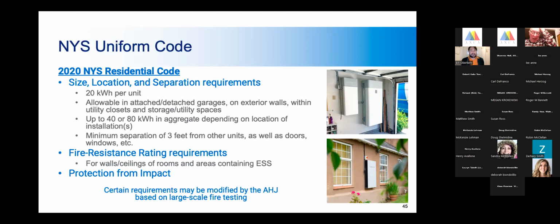So any application needs to make a good solid argument as to how the site for the system is one of those spaces. So we've got a 20 kilowatt hour per unit limit, but we can go up to 40 or 80 kilowatt hours in aggregate. So up to 2 or 4 units, depending on the location. So I think you can go up to 80 on exterior walls and detached garages, and you're limited to 40 in utility closets and attached garages, is how that works. And then we've got separation, a minimum separation of 3 feet from other units, as well as doors and windows. And then we've got fire resistance rating requirements in the residential code as well for walls and ceilings of rooms and areas containing energy storage systems. And right down here, we see certain requirements may be modified by the AHJ based on large scale fire testing, which is the 9540A test once again.